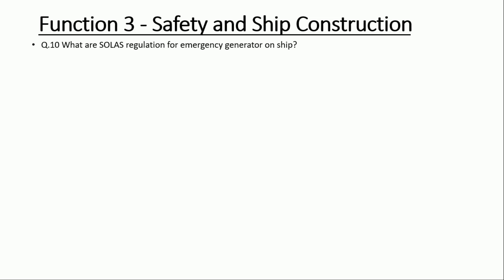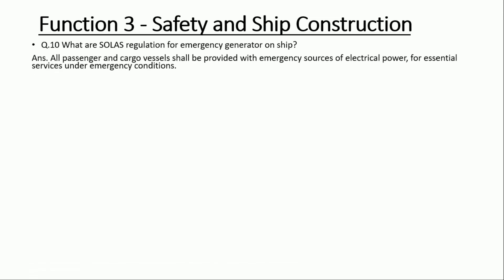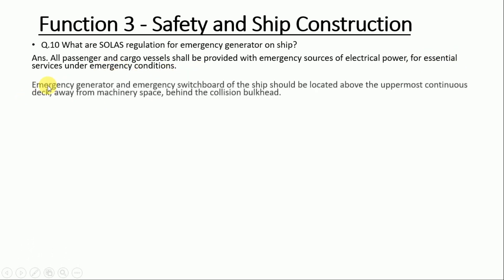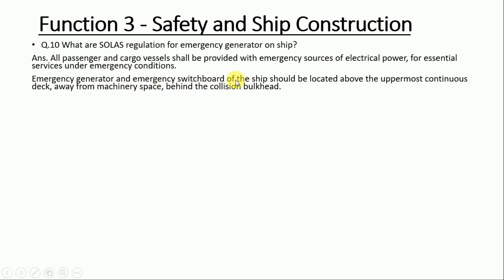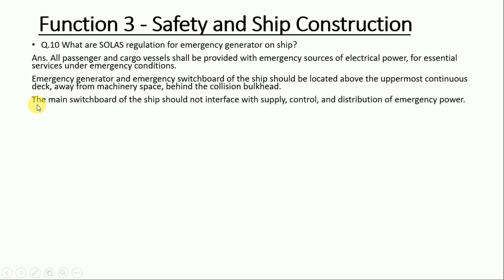Question number ten: what are the SOLAS regulations for emergency generators on ships? All passenger and cargo vessels shall be provided with an emergency source of electrical power for essential services. The emergency generator and emergency switchboard shall be located above the uppermost continuous deck, away from the machinery space and behind the collision bulkhead. The main switchboard shall not interfere with the supply, control, and distribution of emergency power.